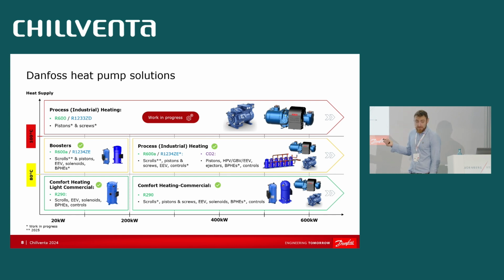For again, smaller sizes, up to 400 kilowatts, we have a new development which is on our booth today, which is approved for isobutane, 100 degrees condensing, scroll compressor, and with ZT as well. We can have 3 of those in a manifold. Today, the swept volume is 140 cubic meters per hour. One compressor, so 3 times 140 can get you to maybe 400, 500 kilowatts, depending on the conditions. Then we also can go with isobutane in our semi-hermetic pistons and screw compressors.